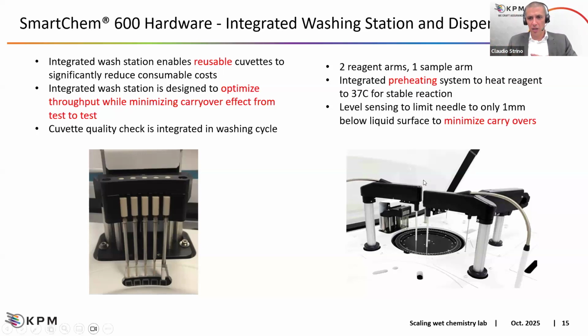We have, as we already said, 2 arms for reagents, 1 arm for samples. On the reagents, we have an integrated preheating system. Why? Because the reagent compartment is refrigerated to prevent any thermal shock of the solution. So to pass from around 10 Celsius degrees to being incubated in a cuvette that is at 37, we pre-warm the reagent in the needle.